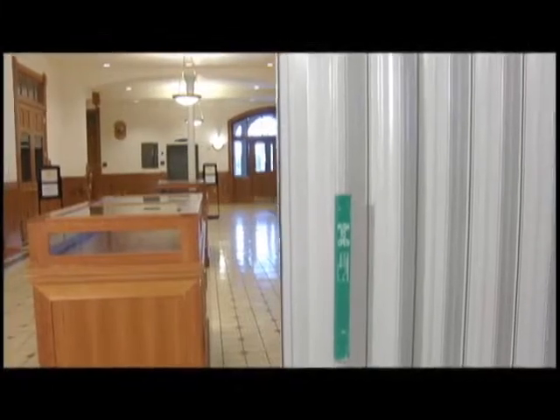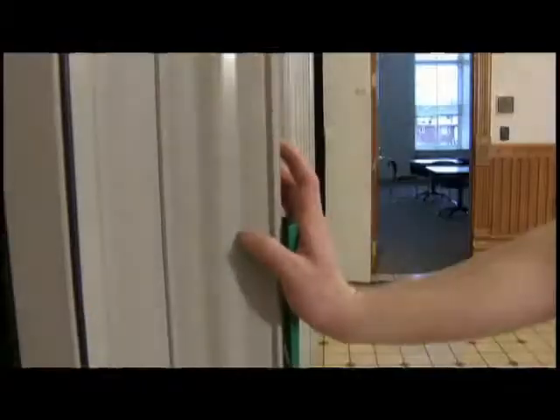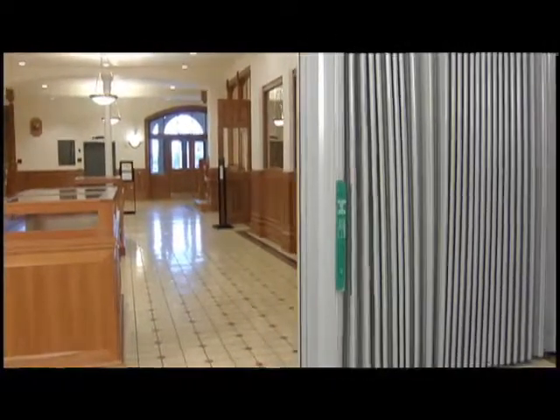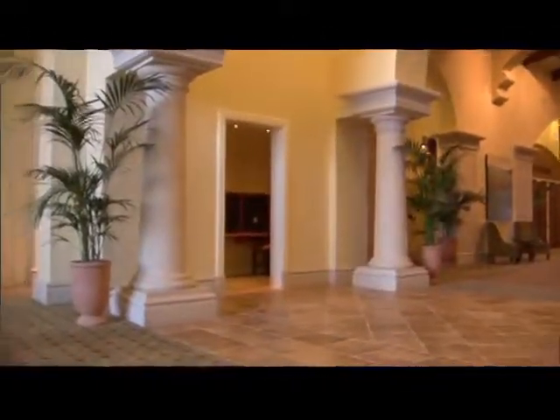The WonDoor FireGuard system is equipped with specially designed fire exit type hardware. This push panel is readily identifiable and responds to only 3 to 4 pounds of pressure. The door will open a preset distance, then pause, allowing building occupants to exit the space, and then the door will automatically reclose. The opening width of the door is flexible and can be programmed to any opening distance.